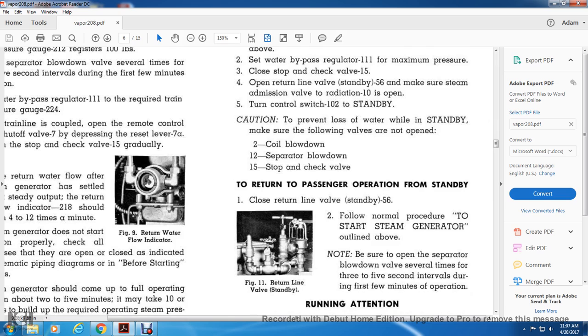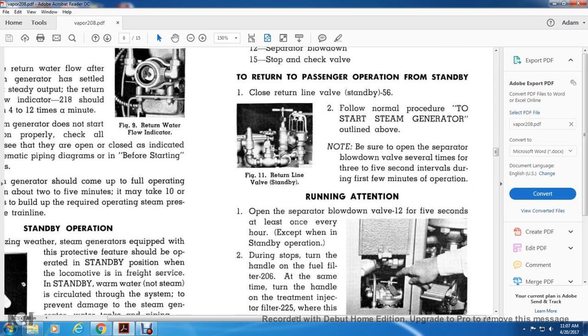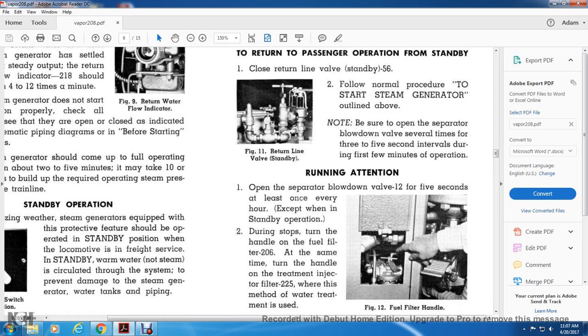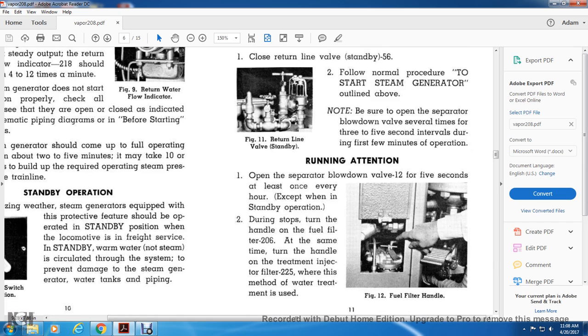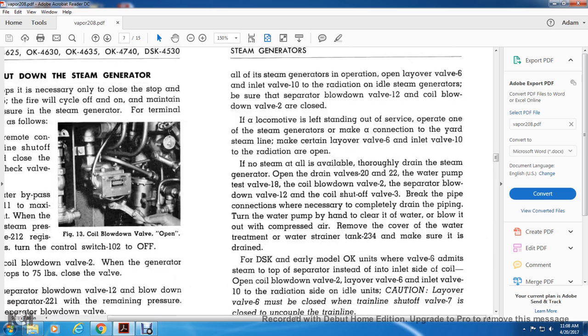Note: be sure to open the separator blowdown valve several times at 3 to 5 second intervals during the first few minutes of the operation. Figure 11 shows the return line valve standby. Running attention: open the separator blowdown valve 12 for 5 seconds at least once every hour, except when in standby operation. During the stop, turn the handle on the fuel filter 206 and at the same time turn the handle on the treatment injection filter 225, where this method of water treatment is used. Figure 12 shows the fuel filter handle.